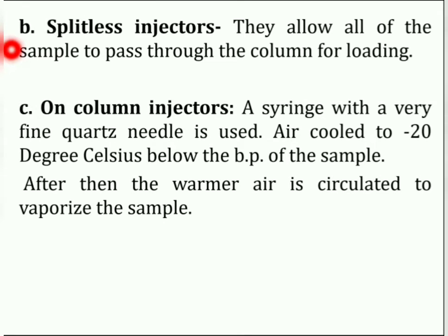Second technique includes splitless injectors. Splitless injectors allow all the sample to pass through the column for loading. In this injector technique, samples should be very dilute to avoid overloading of the column.